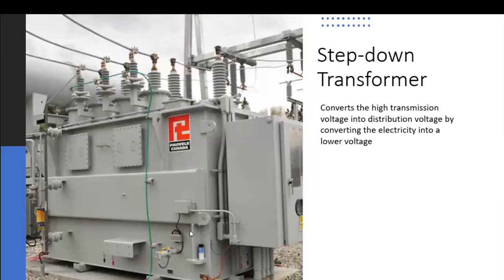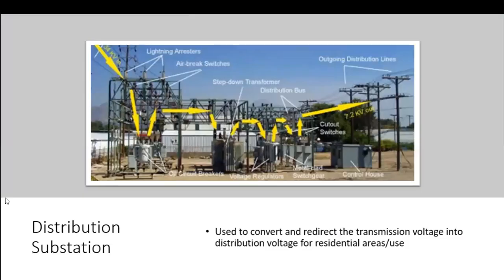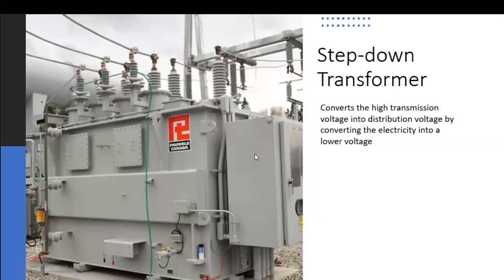As we spoke of before, in the substation, there's a step-down transformer. So we've got transmission voltage on this side, distribution voltage on this side. Right in the middle here is a step-down transformer. That step-down transformer converts the high transmission voltage into the distribution voltage by converting the electricity into a lower voltage. So we're doing it on a real large scale here. You've seen transformers that we've had in class. Those are typically like a 25 kVA or a 10 kVA or 15 kVA. These transformers will go up to 22 MVA, so megavolt amperes.